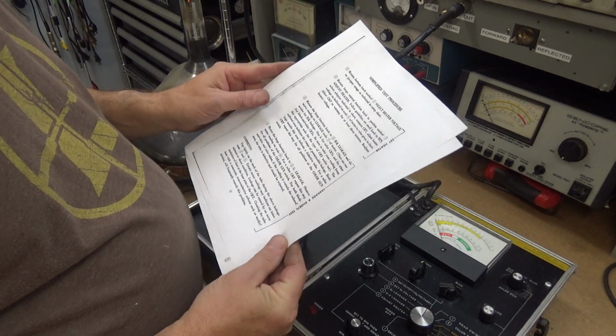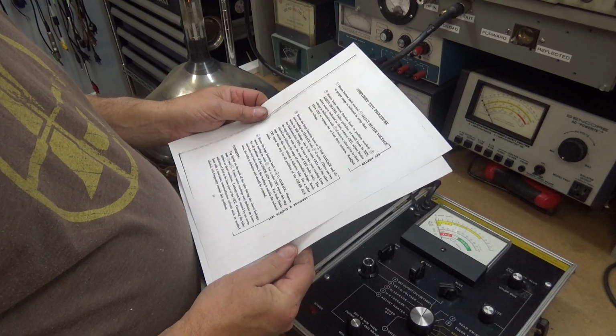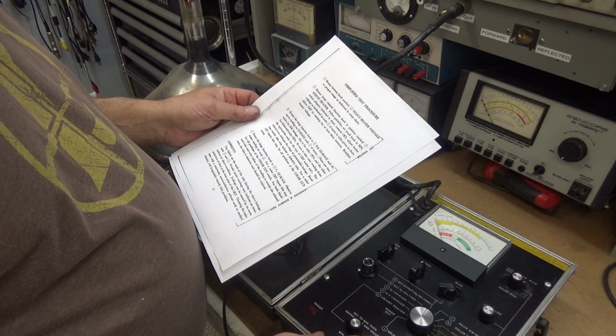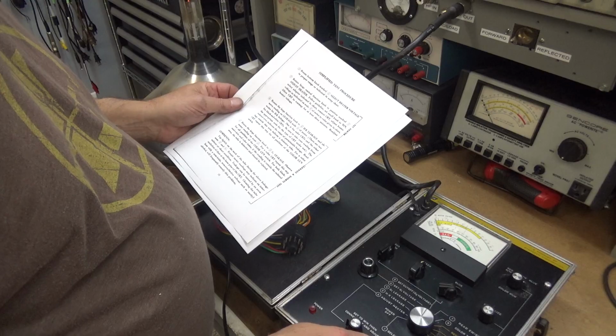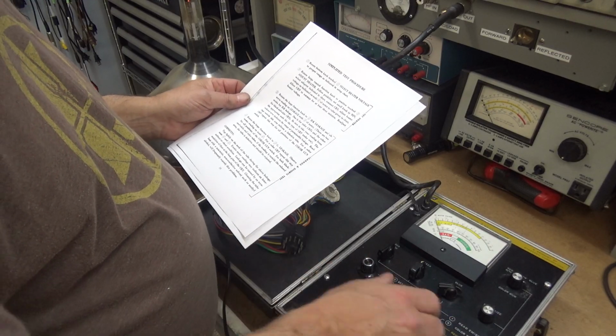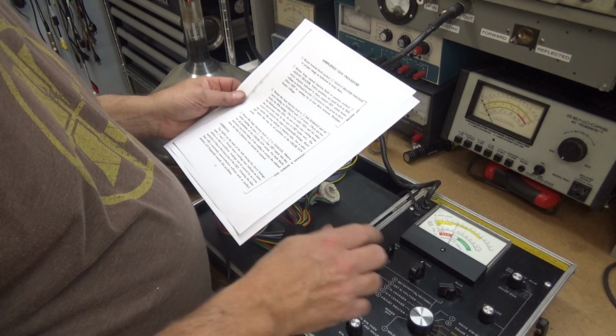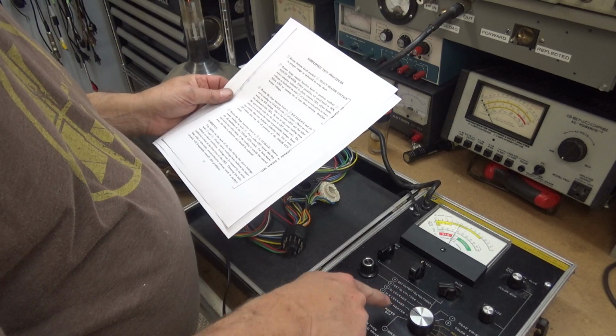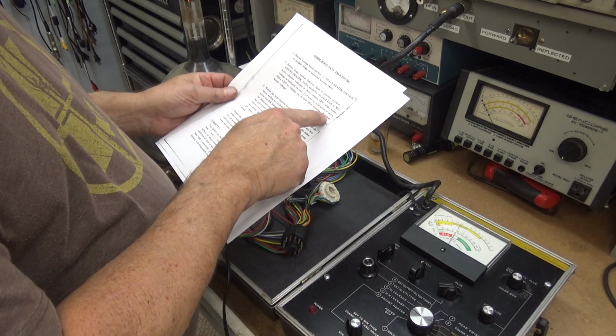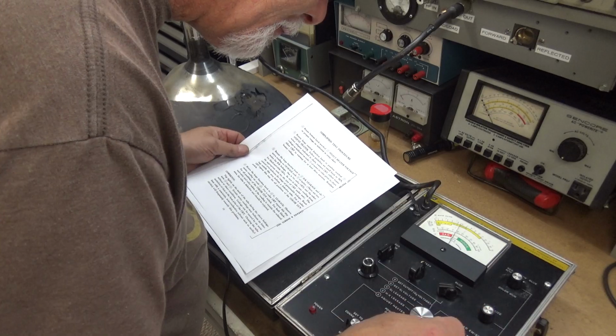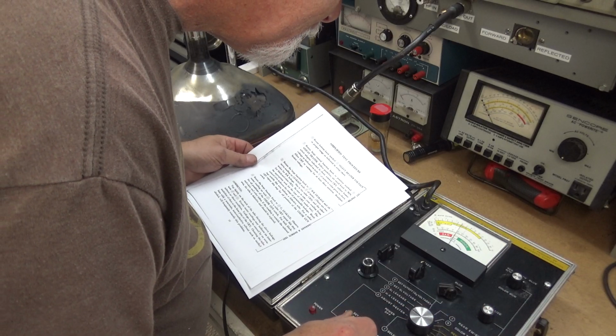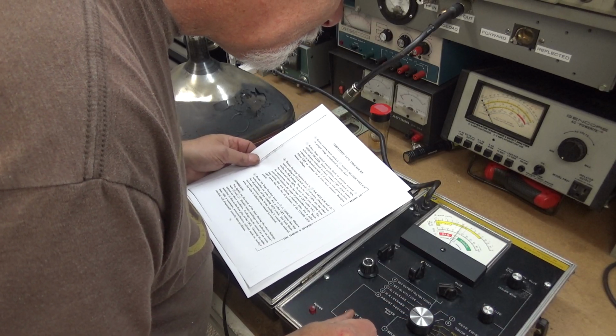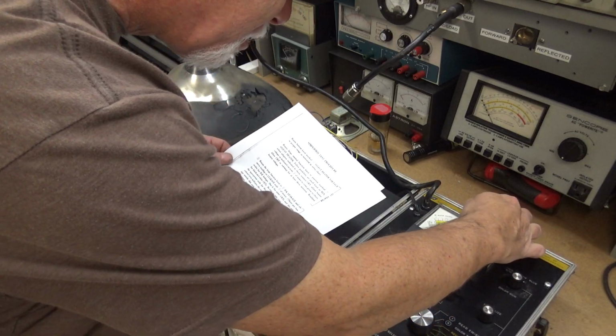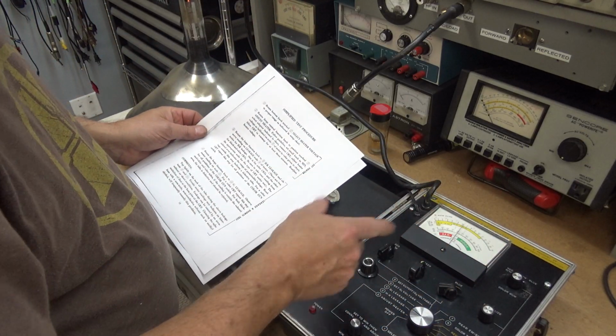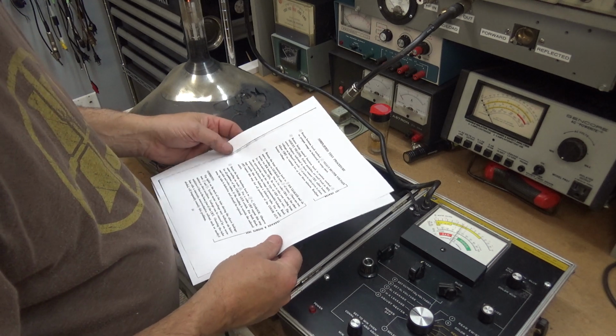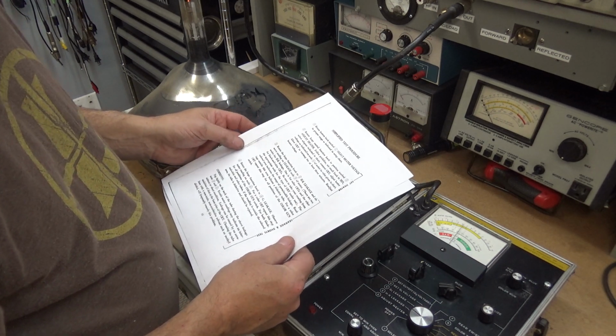Simplified test procedure says number 1, rotate bottom knob marked select heater voltage to proper range as indicated in setup chart, which we have done. Rotate large central function control knob to position marked number 2, which we have. And adjust heater, follow the guidelines here, so we'll just turn this up. There's a little red spot that says 6.3 on there, and we already looked the tube up. The filament voltage is 6.3.